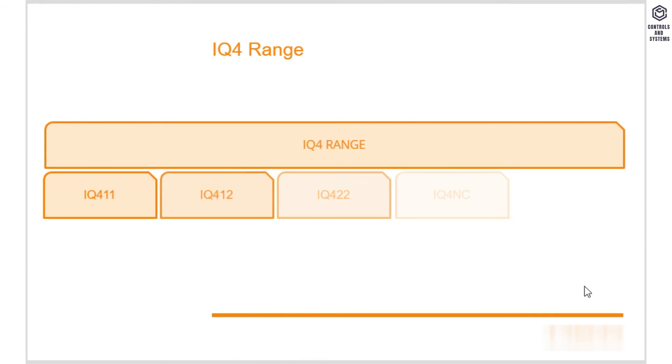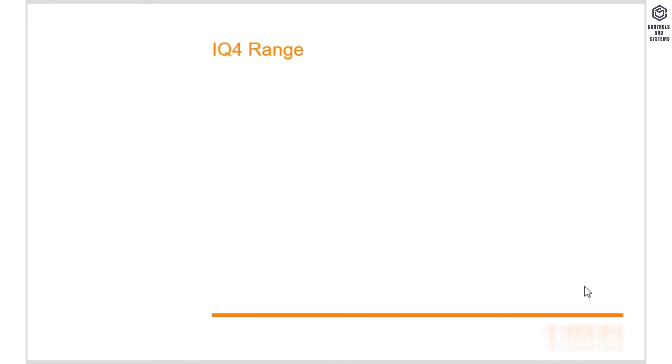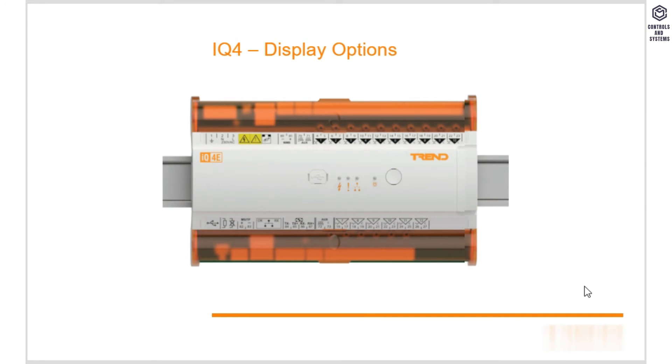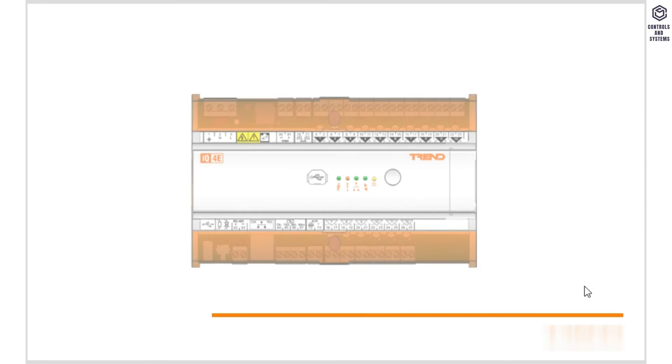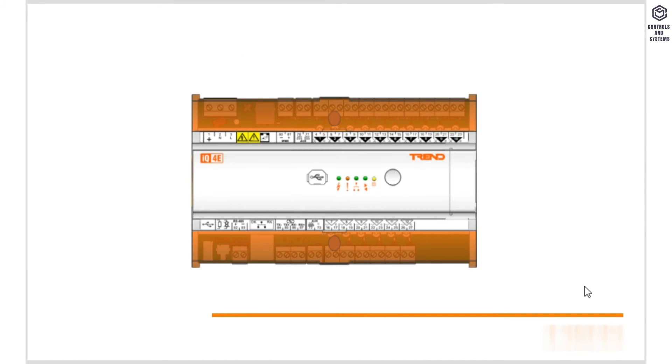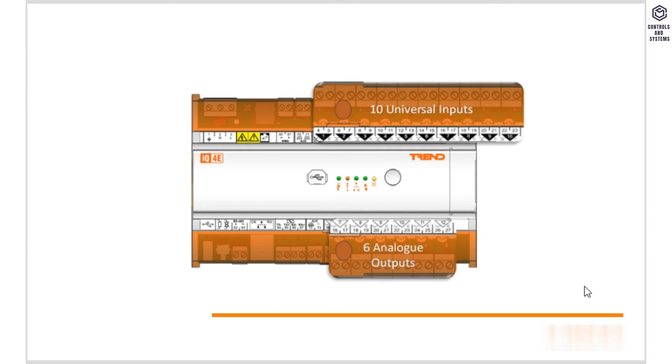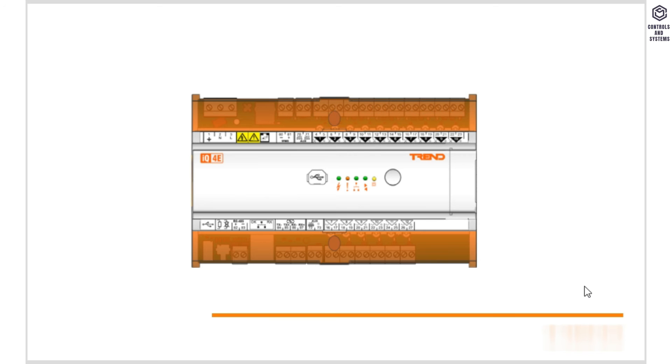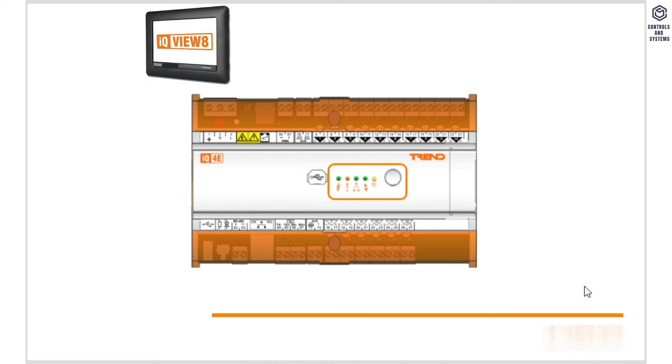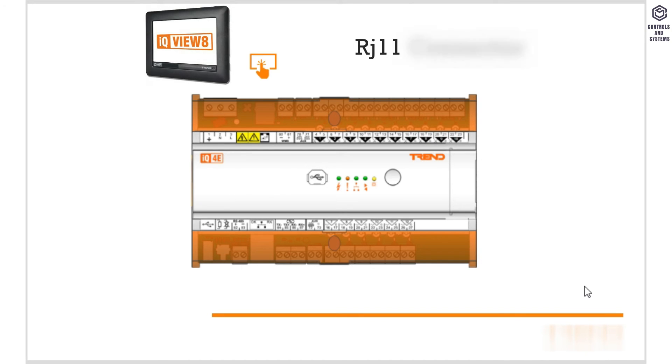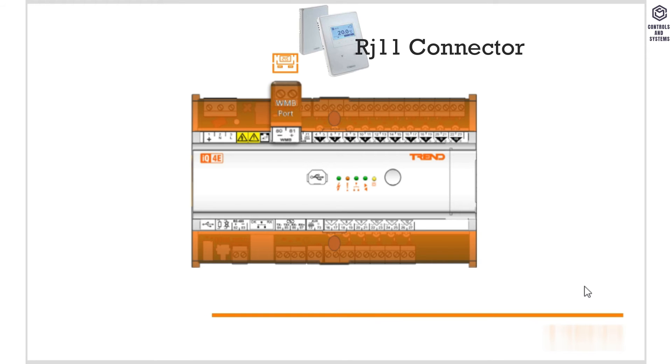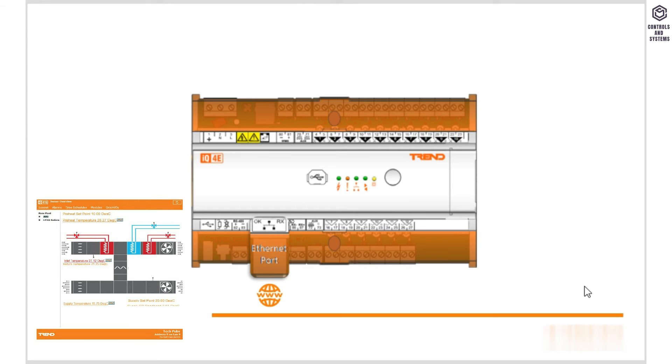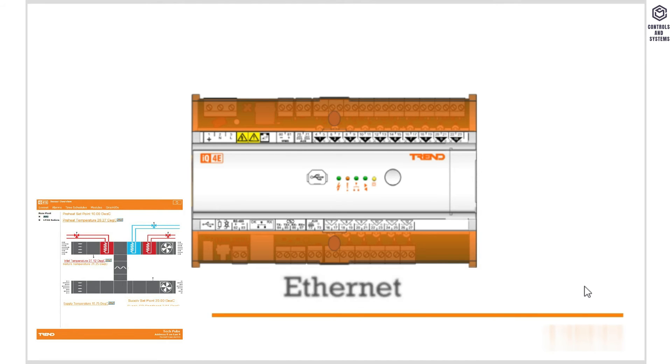There are five models in the range, each with their own specific features. All IQ4 controllers have ways of letting you see what's happening within the device. On the controller itself, there are visual indicators which can be used to get quick status updates. For example, if an input or output is active, the LED next to it will light up. There are also LEDs in the center which indicate the power connectivity status along with the general health of that controller. If we wanted more information, we can connect to a display. These will be covered in more detail in the displays module, but the IQ4 range can connect to Trend touchscreen displays via the RJ11 connector, to WMB local room displays via the WMB port, and using the Ethernet connection, it is possible to access the built-in web pages of a controller. It is important to remember that all IQ4 controllers come with Ethernet connectivity as standard.